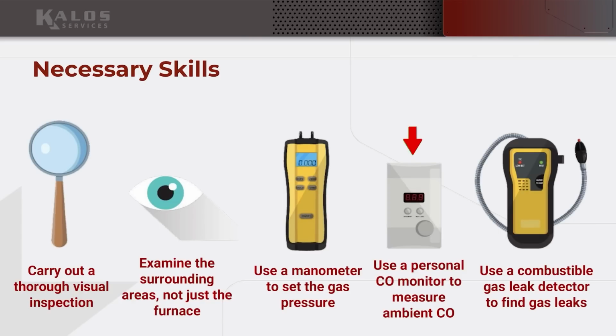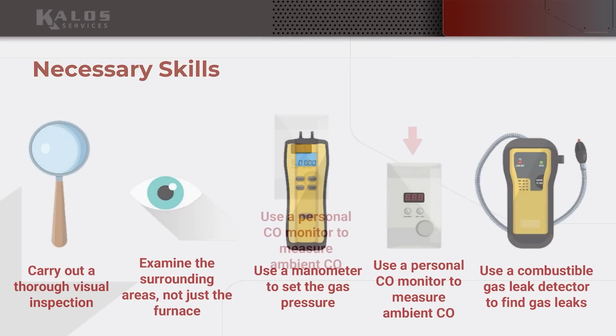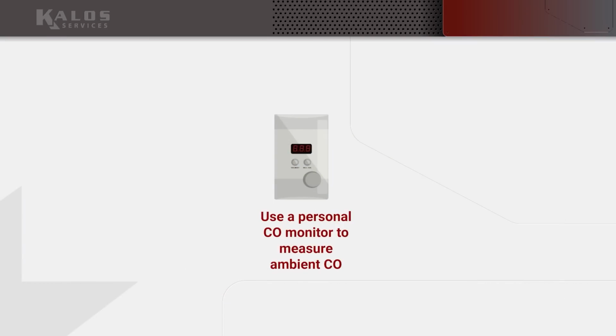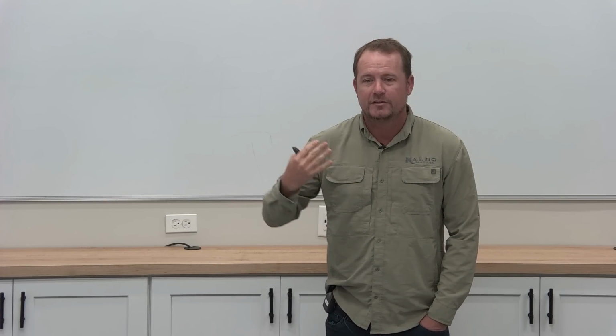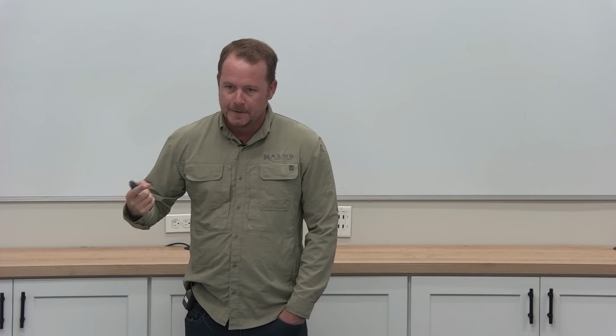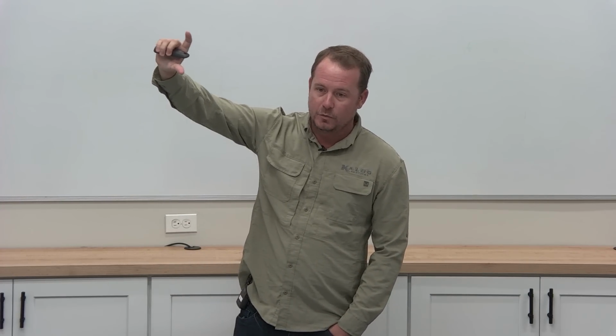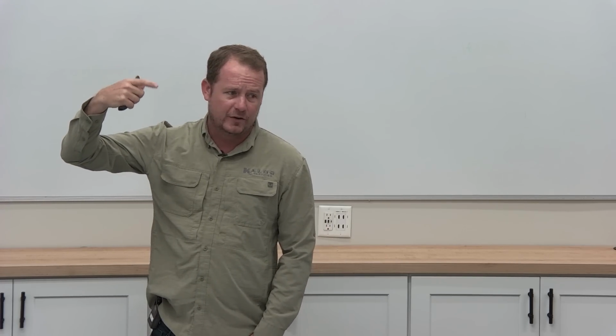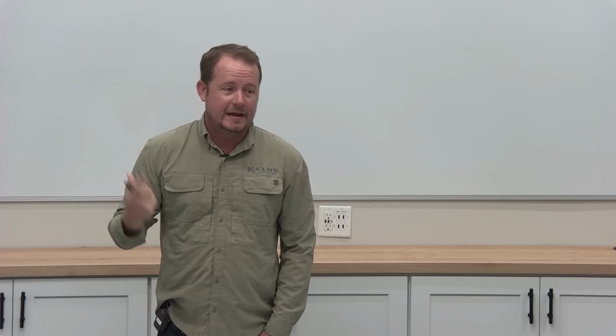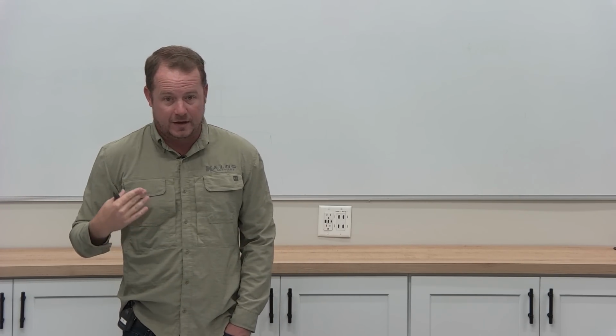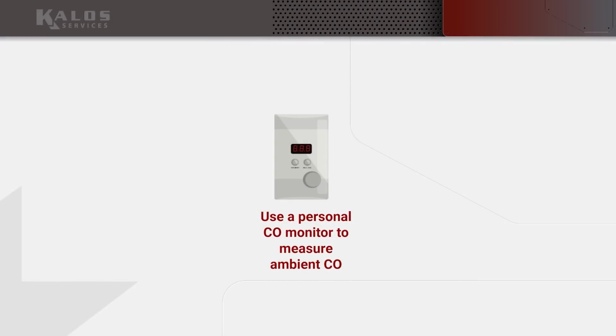The next thing is using a personal CO monitor to measure ambient CO, that little one you keep on you. But there's also a low-level installed or permanent CO monitor that we should be suggesting to all our clients with gas appliances. I've said this a zillion times, but in residential it gets missed because we just don't have as many of these here. The CO monitors inside the house that alarm and are required by law, the UL listed ones, don't start alerting until about 100 or 200 parts per million. So you could have a very dangerous ongoing operational condition making people sick that the alarm isn't catching, and that's where a low-level carbon monoxide monitor is really nice to have.